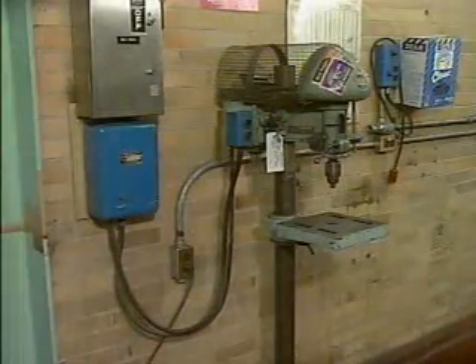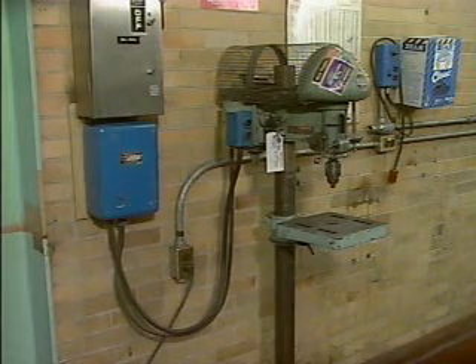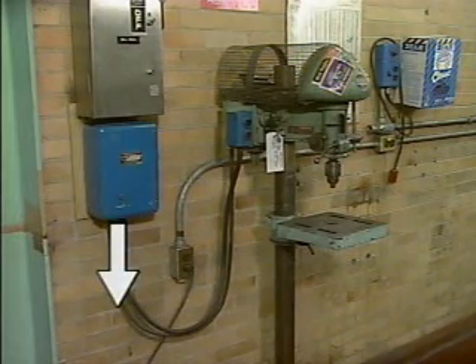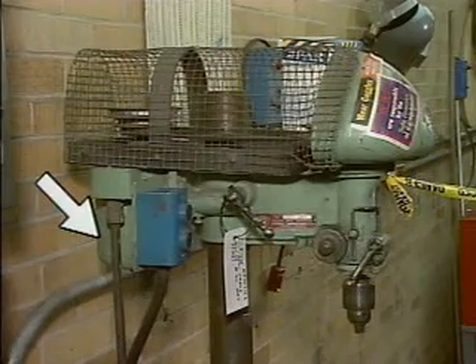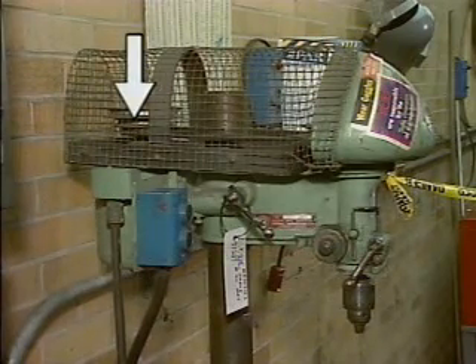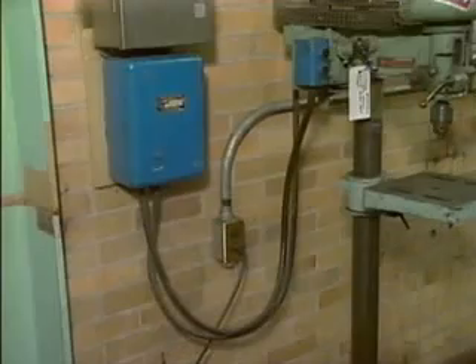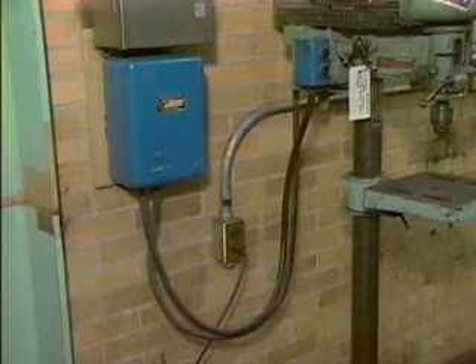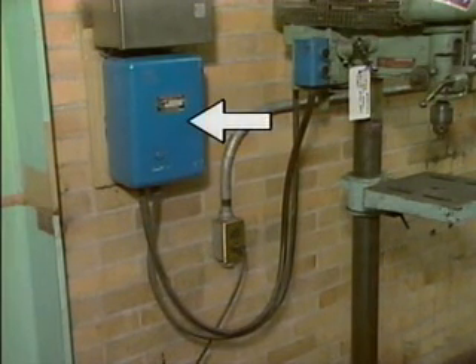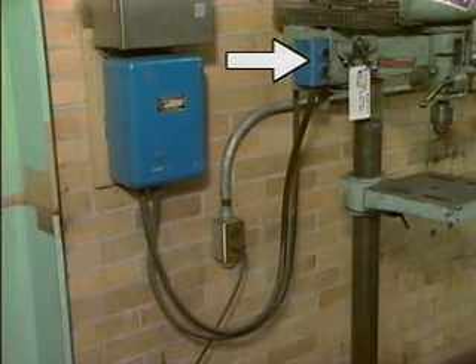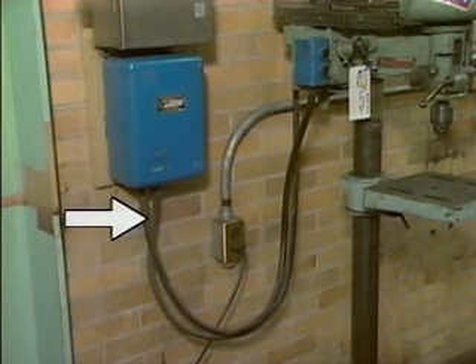This tells the electrician that the cause of the problem is not in any of the wires leading from the control cabinet to the motor, the drill press motor, the pulleys that connect the motor to the drill, or the drill itself. At this point, the electrician has narrowed the location of the cause of the problem to the control cabinet, the push-button station, or the wiring that connects the two.